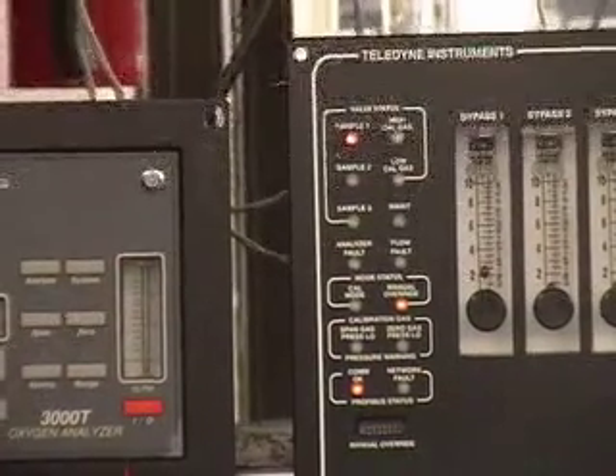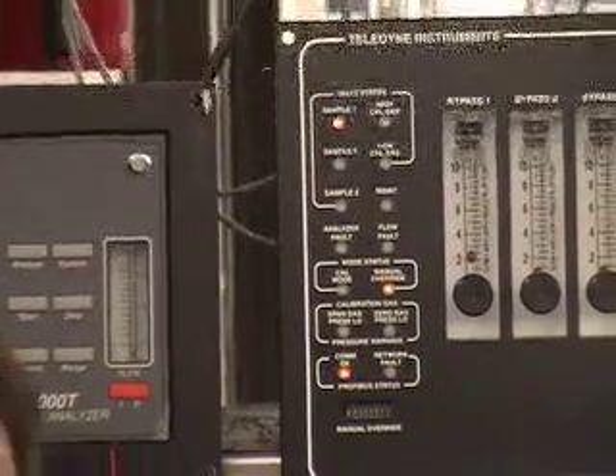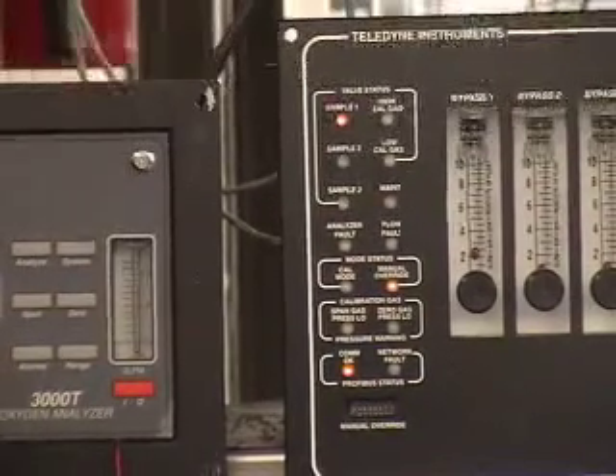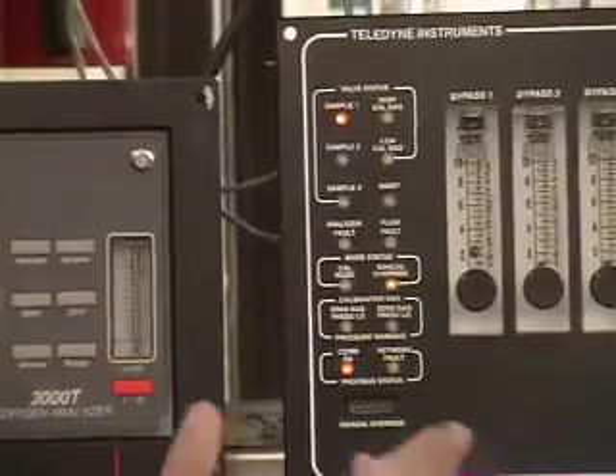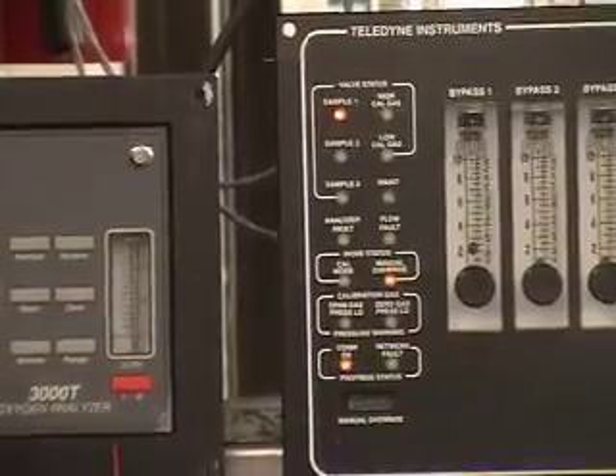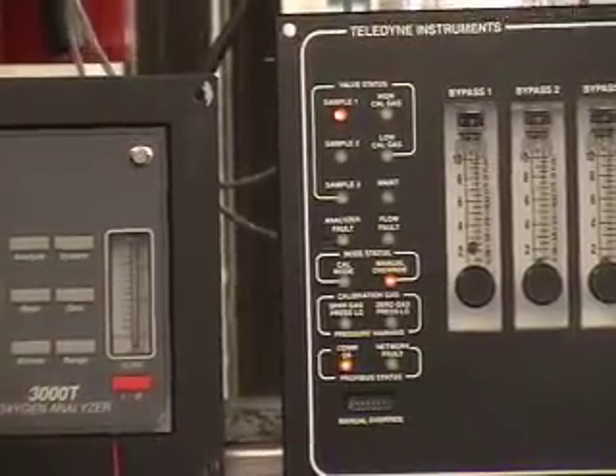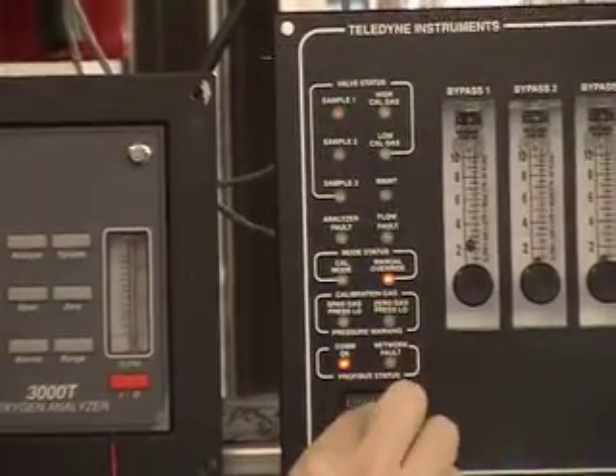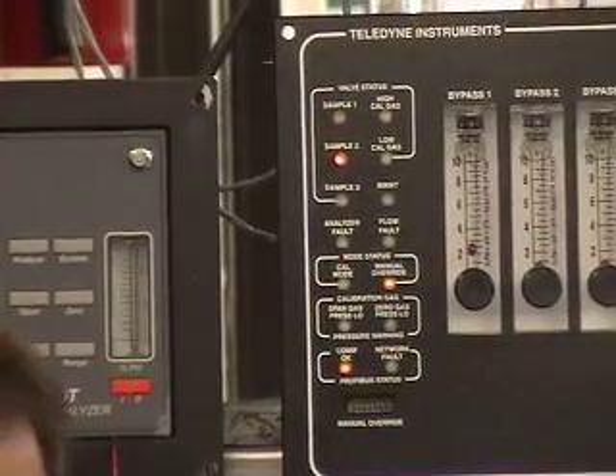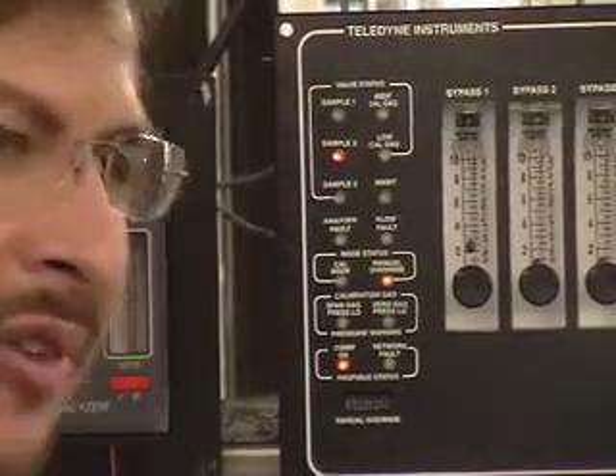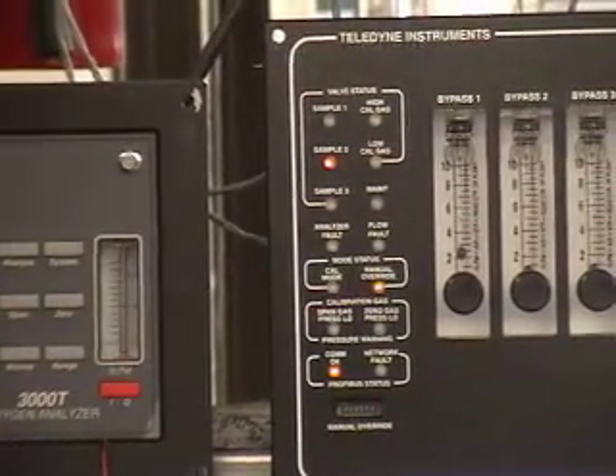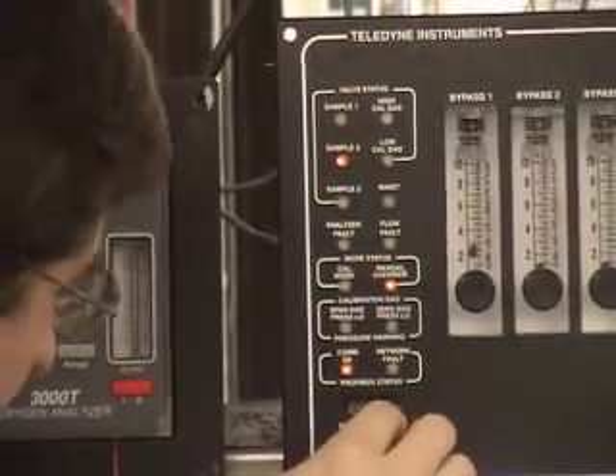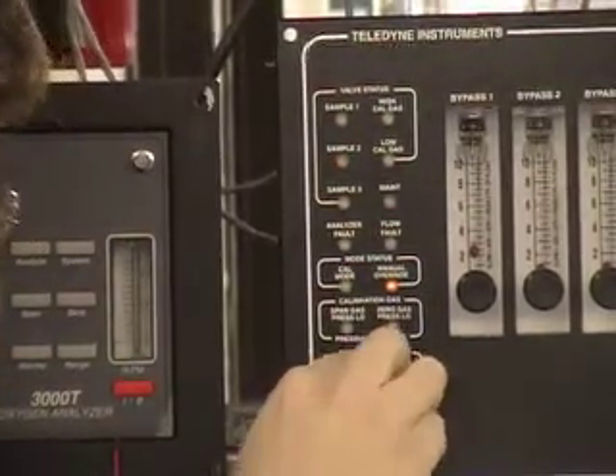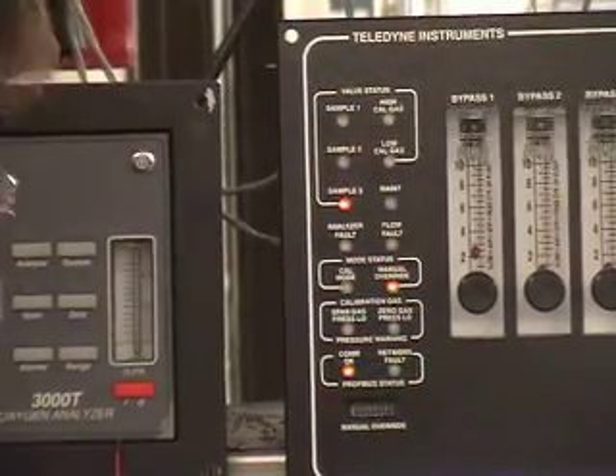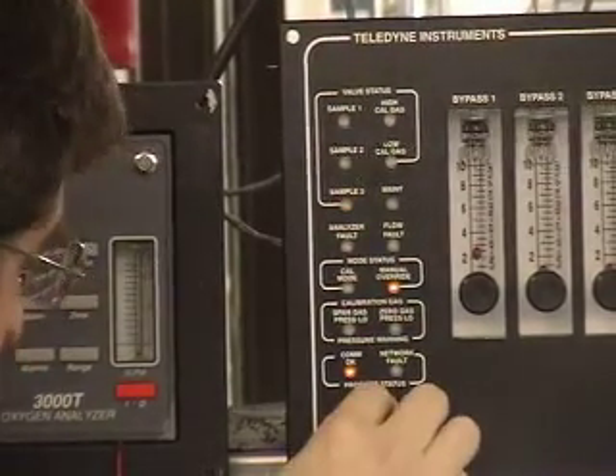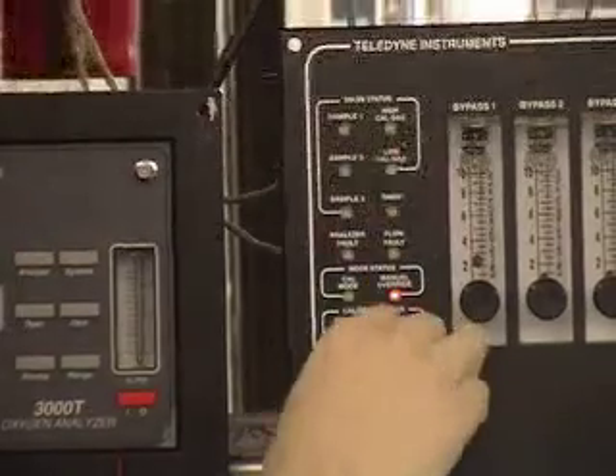So it's ignoring what the PC is sending through the PLC. That's the use of the manual override: to change the valves here at the front and ignore what the Profibus network is asking. Now I can go on to the next one, position number 6, and you can check the manual. If you cannot see what I'm doing, you can check the manual to see which DIP switch will do what. So I have control of that one as well. I have control of the next one, sample 3, and the next one will be, of course, the high cal gas.